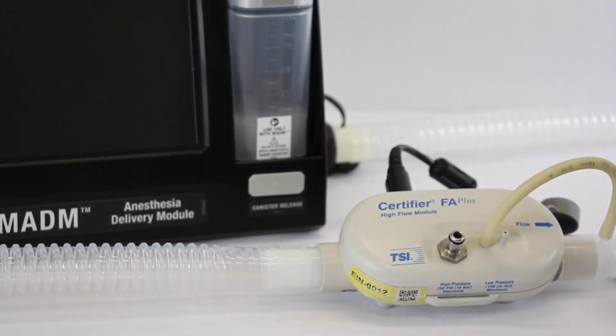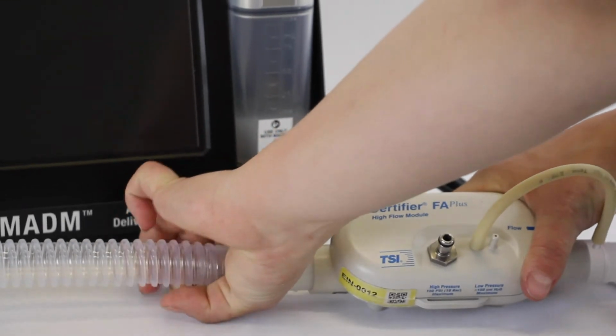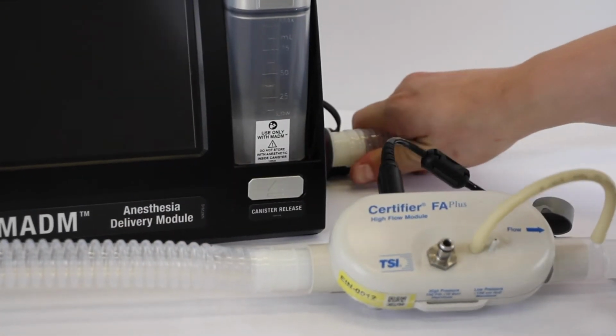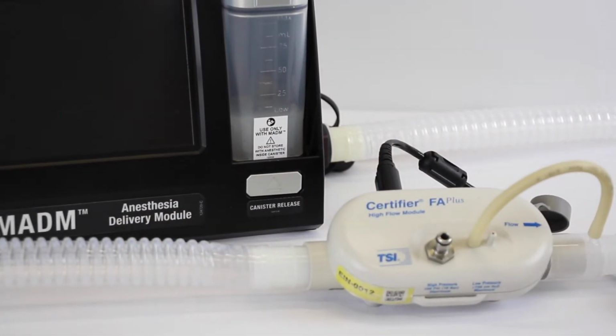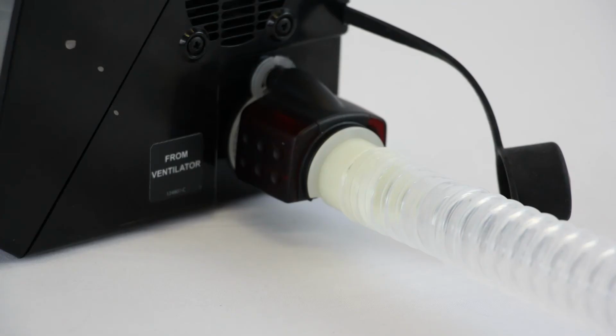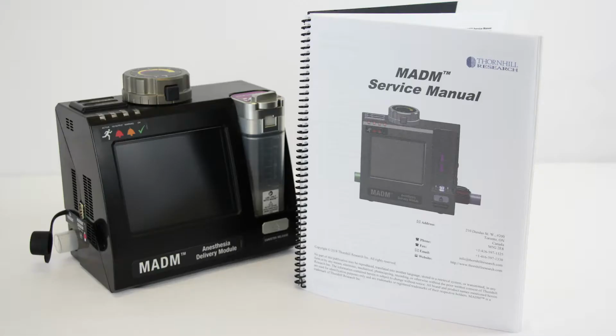In the event that the flow reading is greater than 0.5 liters per minute, confirm that all components of the test setup are securely attached and not leaking. If the leak persists, confirm that the inlet sensor is installed completely on the device. Otherwise, refer to the MADM Service Manual or contact Thornhill Medical for support.